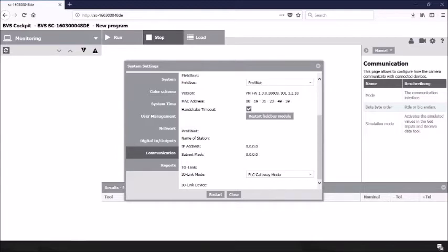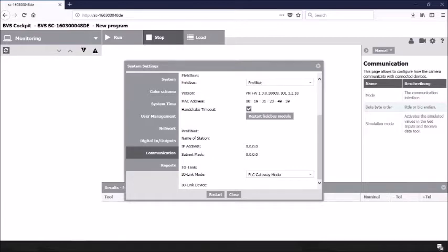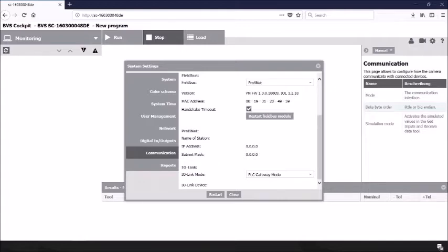Next is the station name. You have the choice to see what the station name is by default or change the station name in some cases. Next, you will see the IP address for the field bus IP address. In the case of PROFINET, you will have a choice of an IP address and a subnet mask back to the PLC. Finally, you have IO-Link mode. Generally, PLC gateway mode is typically what's used for the IO-Link mode for the connection of this port. For additional information on these settings, refer to the manual or contact tech support.